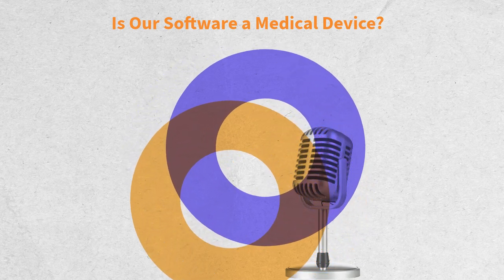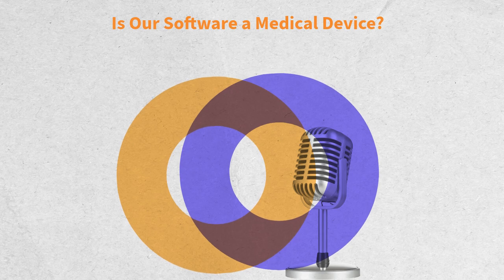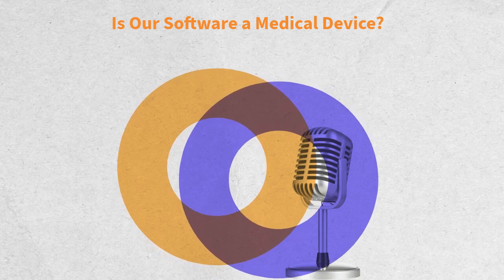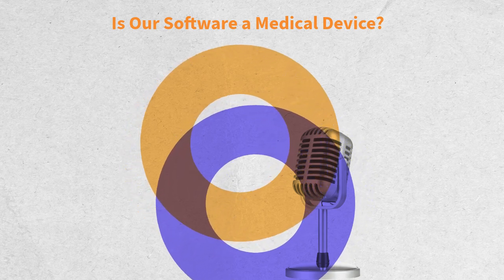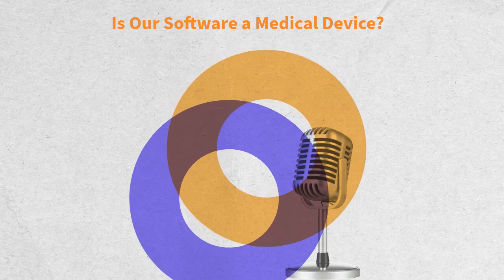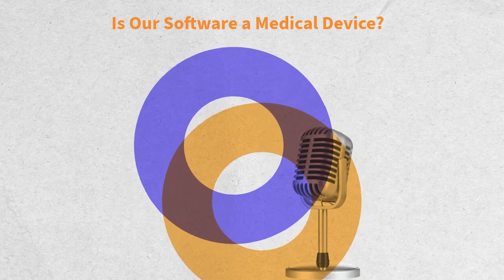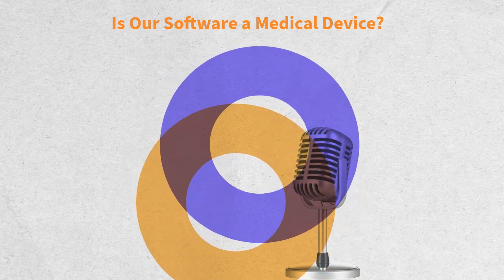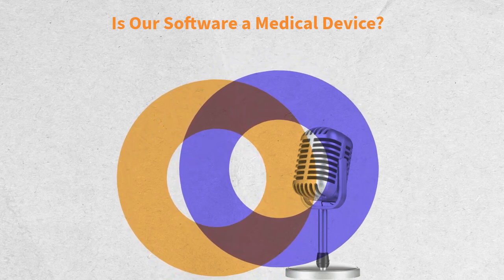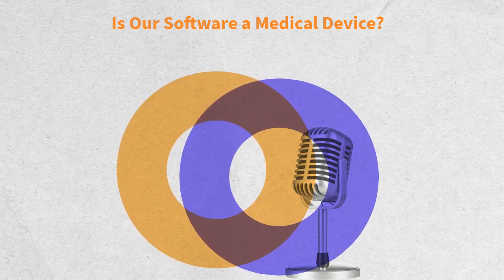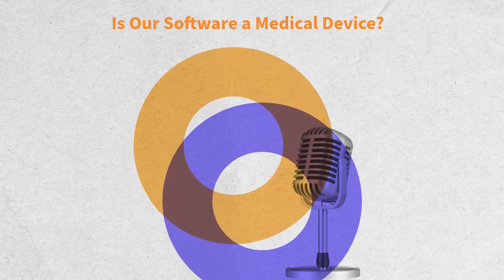Under Directive 93/42/EEC, the MDD, much software was classified in Class 1 because there was no specific rule. Under the MDR, Rule 11 in Annex 8 was introduced, dedicated just to software. Before, with the MDD, there were gray zones and much interpretation. After, with the MDR, Class 2A, 2B or 3 depends on the clinical function and on the risk.